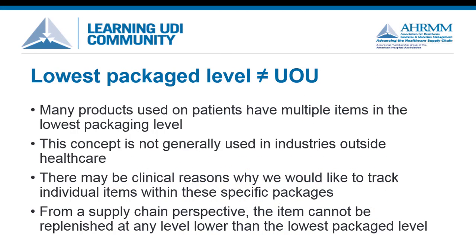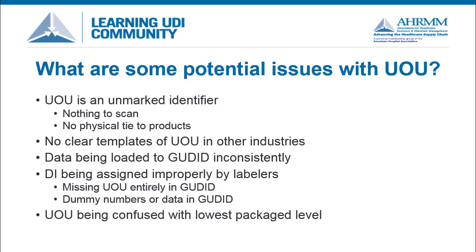While this may seem like a simple idea, there is a lot of confusion with this concept, as there is no precedent for it in other industries. The term 'unit of use' may seem to imply that it is the same as the lowest packaged level, but this is not the case. In most supply chains, you are not able to distribute product in any form lower than the lowest packaged level. This is especially true for items which are packaged to sterile, as these items are no longer considered sterile once the package is opened. In healthcare, there may be clinical reasons why we need to track the individual items below their lowest packaged level. The Unit of Use DI allows us to differentiate between the individual device and the grouping at the lowest packaged level.